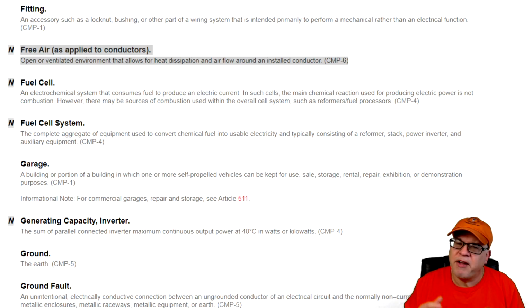So what if I hung a cable on a messenger and the cable was covered? Maybe it was a tray cable that was being hung on a messenger. Then you had the sheathing, and you could not use the free air ampacity values because you really didn't have the free air aspect of it. So again, this is free air as it applies to conductors, not cable assemblies, to conductors, all right? So now we have a definition. We know when we can and can't apply free air, especially when we're dealing with ampacities. Of course, we'll deal with that when we get there, okay?